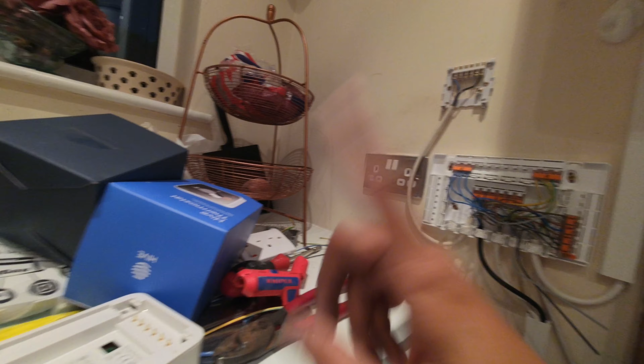I'm going to be changing the PCB anyway, so I need to rewire the terminals inside there. I've also noticed that as well, so I'm going to grab a grommet from the van and change that over as well. And then one of these 2 cables will be our switch live, going back to the boiler, so once I know which one's which inside there, one of these will get snipped and one of these will go into there, because these 2 black cables are basically coming off of the orange cables on here for our switch live. So I'm going to power up the hub first for the Hive, because that takes ages, and whilst that's powering up, I will then sort out the wiring in here and sort out that grommet, etc.